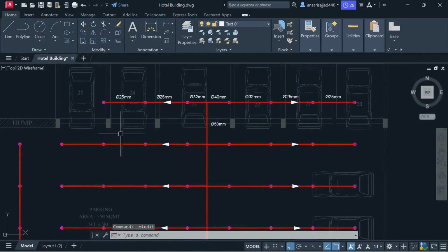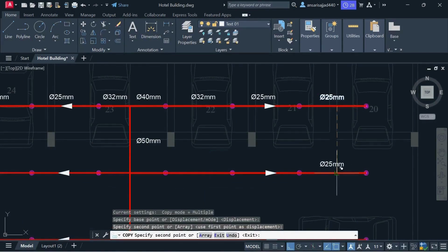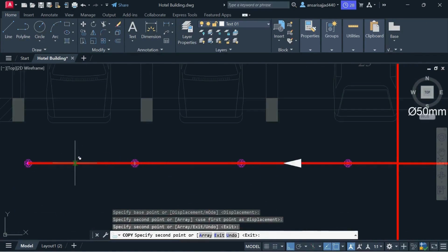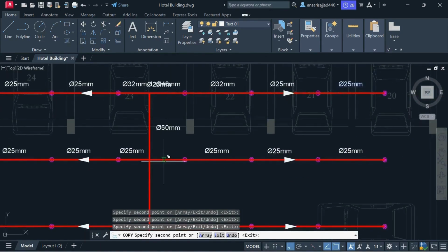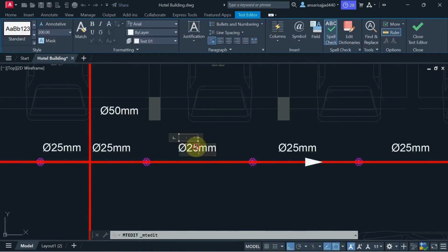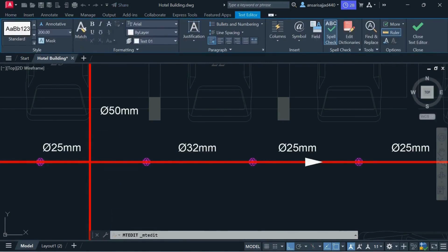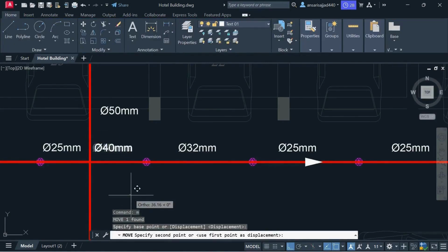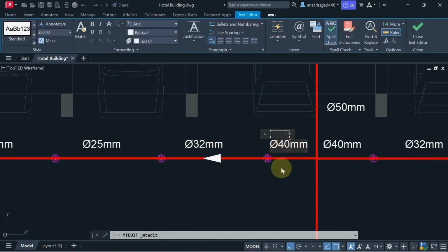Okay. Same way for all these branches, the process is the same. Just use it and copy it here. For this one, here also up to 2 sprinklers, pipe size 25 mm. So I have written here. Clear? See, 25 mm. If your number of sprinklers is more, the pipe size is 32. And here the pipe size you will get is 40. Clear? So all this we have discussed already. Same way here also, the number of sprinklers is more than 2. So go for 32 mm pipe size, and here 40 mm.